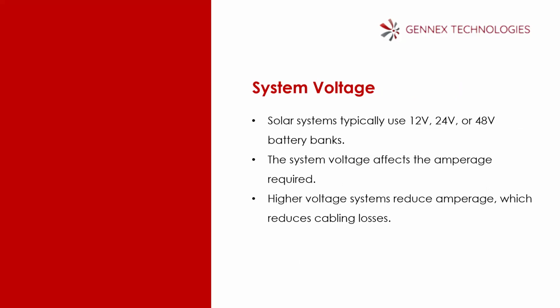Now, system voltage. Of course, you need to know what the system voltage is. We have different types of inverters, for instance, or chargers. They have voltages they operate with. We have 12 volt inverters, we have 24 volt inverters, and we have 48 volt inverters, and we have higher voltages too, but these are the common ones. Now, the system voltage affects the amperage required. If your load is much and you want to use 12 volts, then the current will be high.